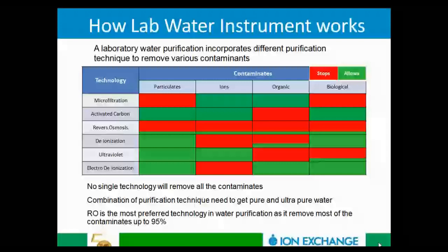So it is very important to have different purification techniques aligned and designed in various steps into a single box to deliver pure and ultra pure water. And these form the consumables, which have to be replaced at regular intervals to ensure that you get the desired water quality. The life of the consumable will completely depend on the feed water quality, the variation in the feed water quality, and the amount of water that has been used.